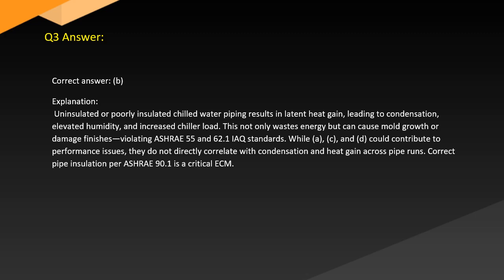Uninsulated or poorly insulated chilled water piping results in latent heat gain, leading to condensation, elevated humidity, and increased chiller load. This not only wastes energy but can cause mold growth or damage finishes, violating ASHRAE 55 and 62.1 IAQ standards, while A, C, and D could contribute to performance issues. They do not directly correlate with condensation or heat gain across pipe runs. Correct pipe insulation per ASHRAE 90.1 is critical.